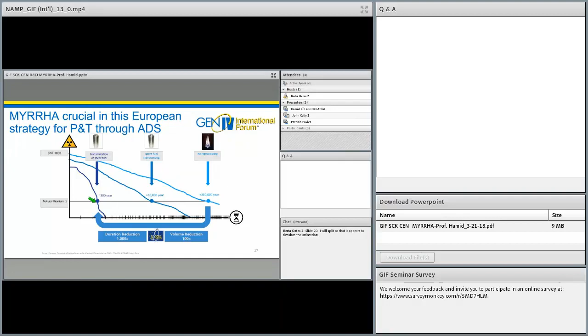But now let us see what MYRRHA is. MYRRHA is an ADS. We want to demonstrate the ADS at pre-industrial scale, and it can operate in critical and subcritical mode. The power of the reactor ranges between 65 and 100 megawatts, so the maximum power of the reactor is 100 megawatt thermal. K-effective 0.95. Fast spectrum, because we are using lead-bismuth eutectic as a coolant. As it is subcritical, we need a source in the center, which we create by shooting a proton beam of 600 MeV, 4 milliamps at maximum, on a lead-bismuth target in the center that generates an intense neutron source in the center of our reactor.